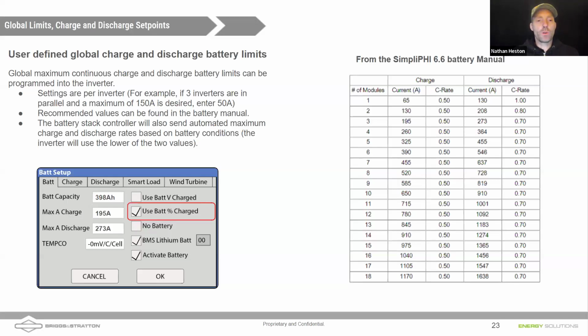And so the battery will communicate what it's happy to take, and you can set in here what the max value you'll allow will be. An example of that might be in my shop, I don't have huge cables coming in to charge my inverter. So I want to limit how much overall power I'm drawing, and I don't want that charge limit to be high like this. 195 amps, at 50 volts, we've got a lot of power running through cabling, right? So you want to be able to limit that.